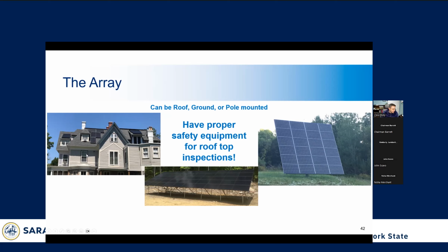There may be access issues, right? It doesn't look super easy to get up here. And this is a great example of where construction photos provided by the contractor are valuable. Because if you have photo proof that they're all the same kind of panel, and you can just check one of them, then you don't have to get up on all these different sections of roof, and that reduces the hazard to you. And you can see, obviously, ground mounted and pole mounted arrays may be easier to access, the different connections, and get the nameplate information, things like that.